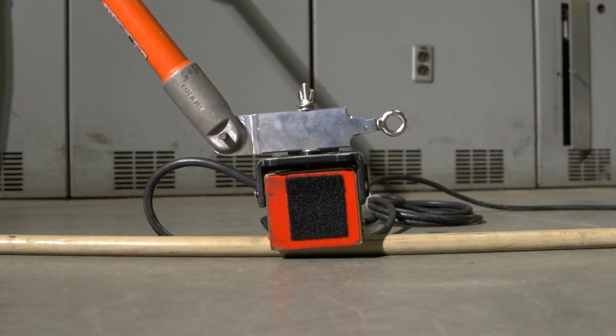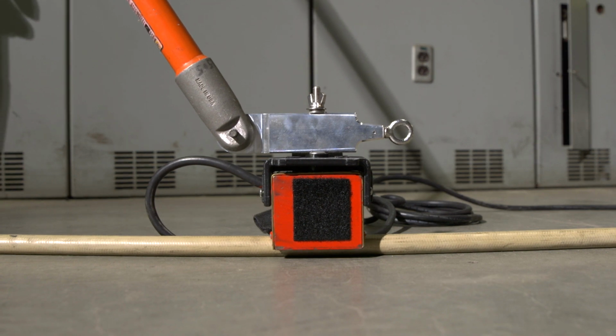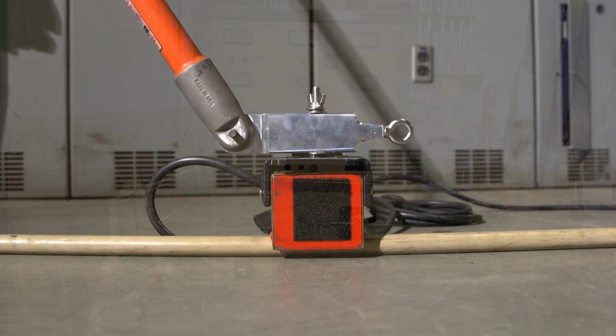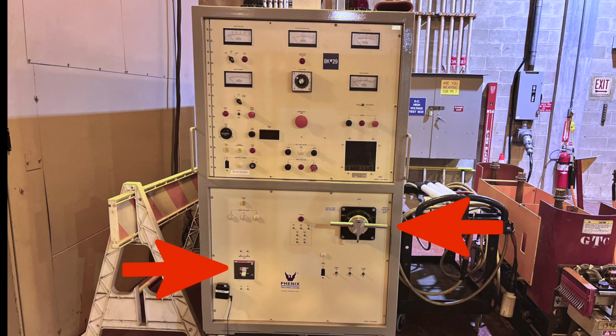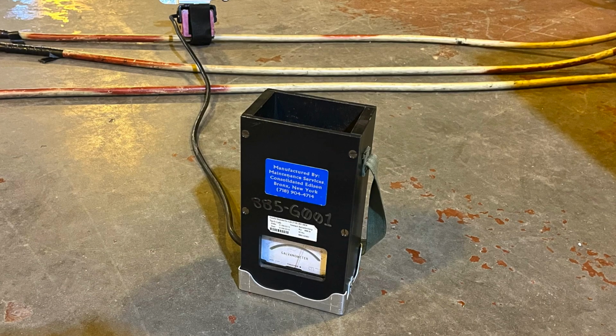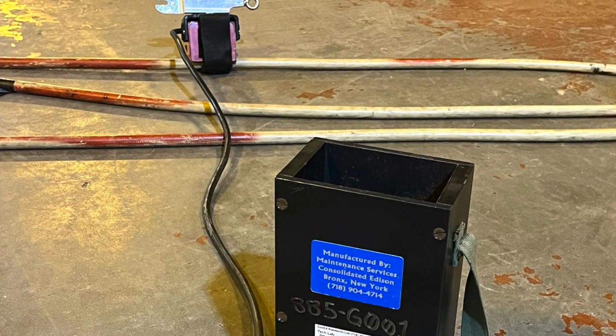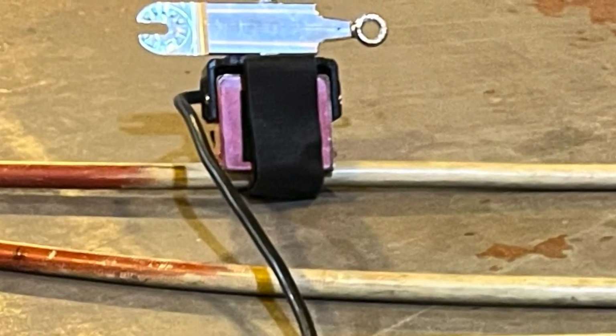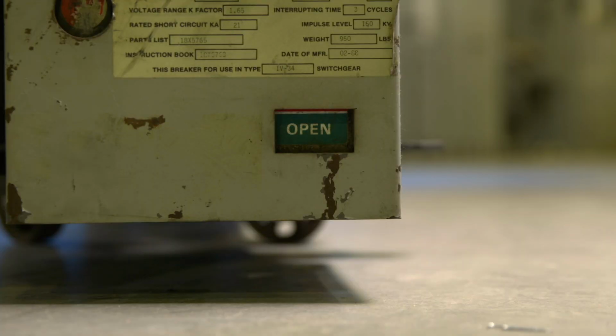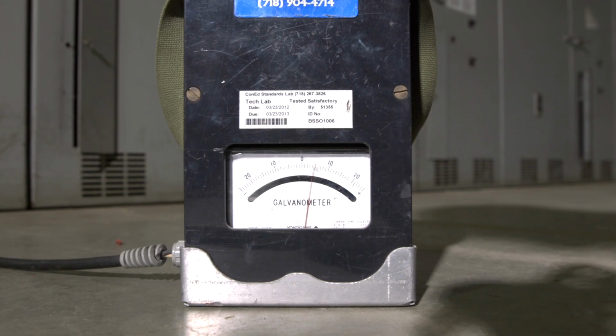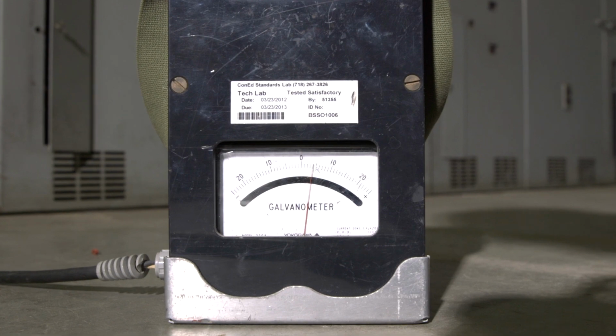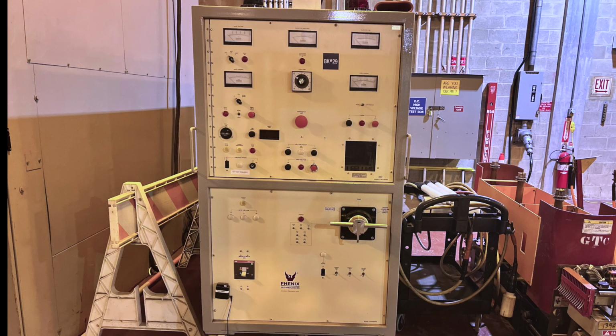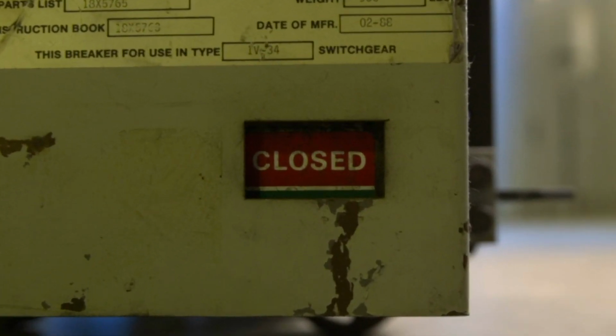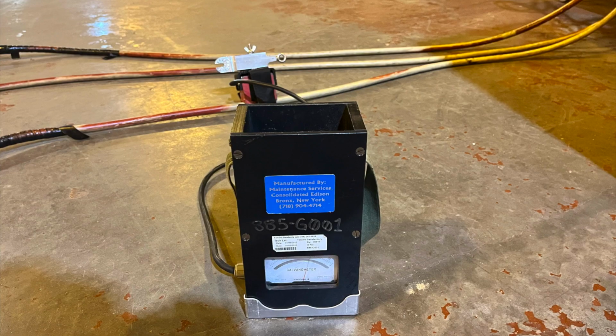If you are unable to perform this job function using a test stick or a shotgun stick, there are alternative methods to perform this test. First, with the high voltage set off and the feeder grounded, place the galvanometer coil on the A-phase lead. Use the Velcro strap to secure the coil to the lead. Turn on the high voltage set and open the ground breaker. Check the gauge on the galvanometer to see if there is any activity. After the phase is complete, turn off the high voltage set, ground the set, and close the ground breaker. You will then repeat those steps for B and C phases.